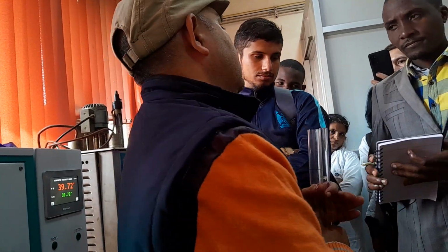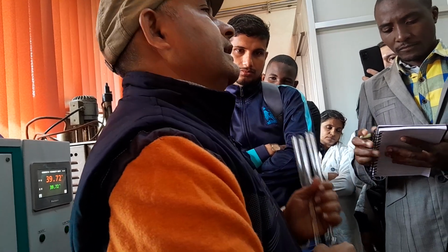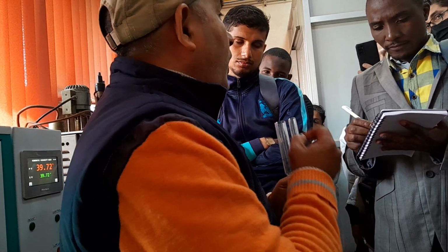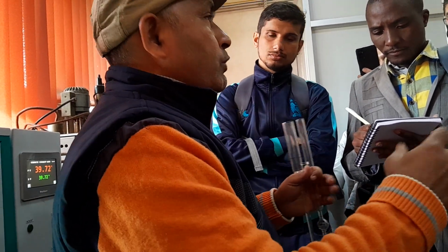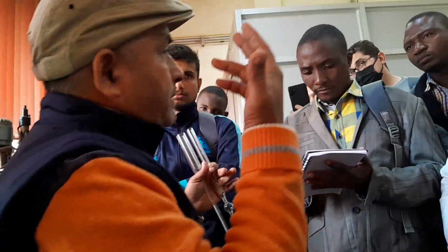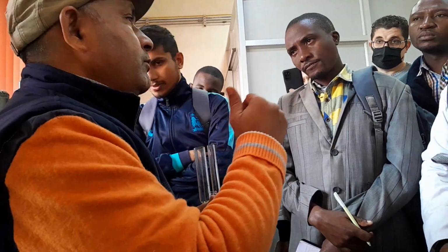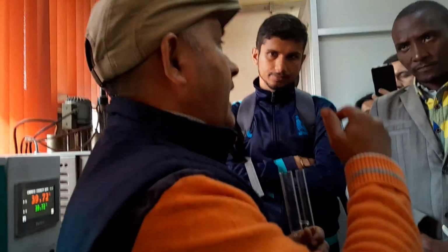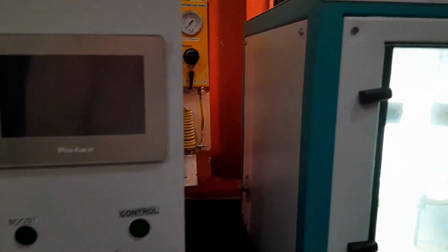Here the minimum flow timing should not be less than 200 seconds while you are doing the kinematic viscosity. Now the question is what will be the maximum time. You can take maximum time, whether it is 4 hours or 5 hours. But if you have 20 samples, you will have to finish them in one day. As I told you, you can take 5 hours or 8 hours, but can you finish all those 20 samples within one day? Not possible. So the maximum time doesn't matter, but you take only as much time as lets you finish your work.